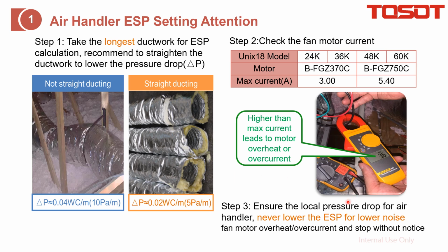please never do that, because if the local pressure drop is higher than the air handler ESP setting, just like what I have introduced, it will lead to overheating or overcurrent of the fan and the fan will stop. And if the fan stops, then there's no warning or error code in the display.